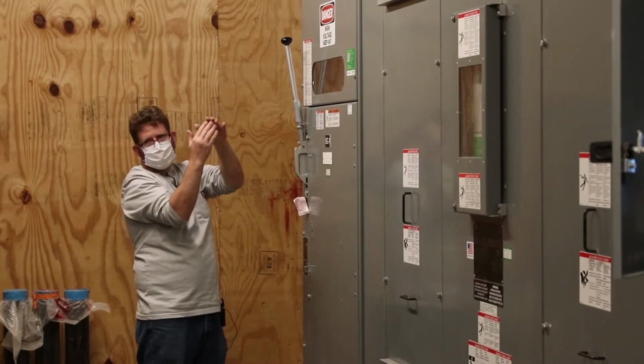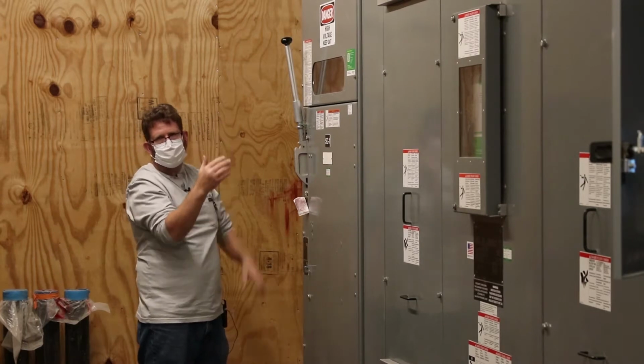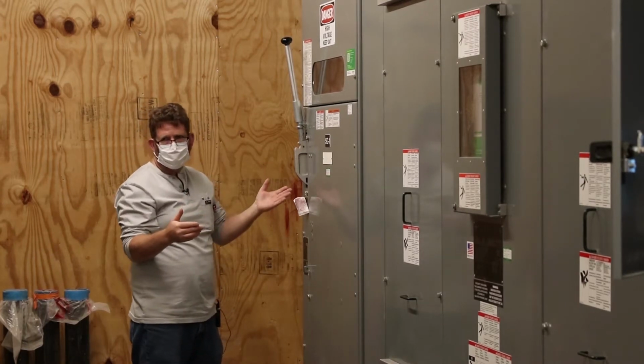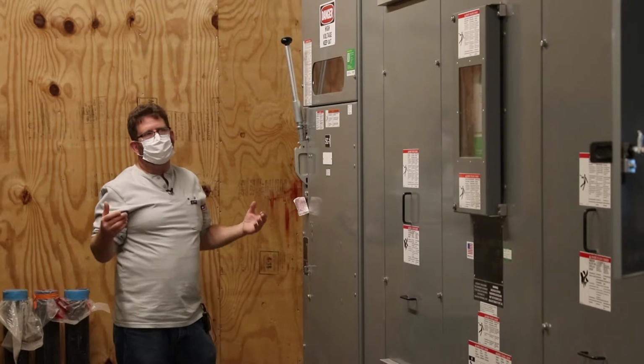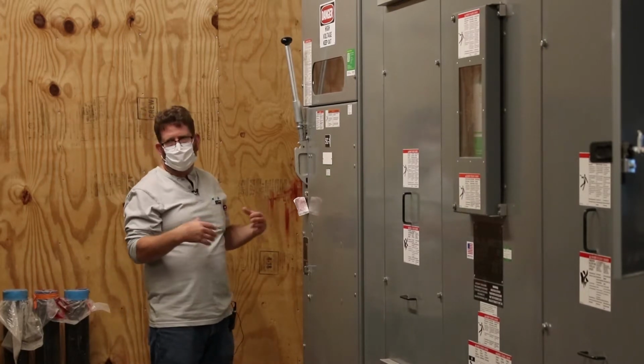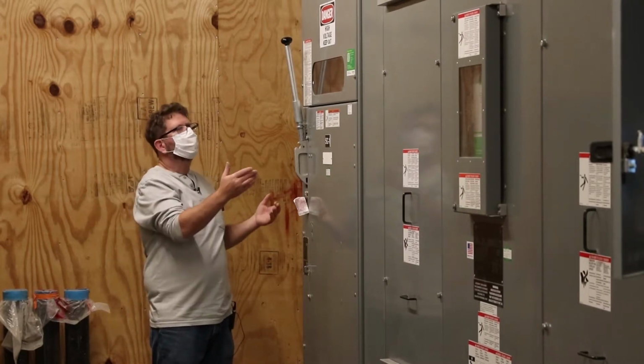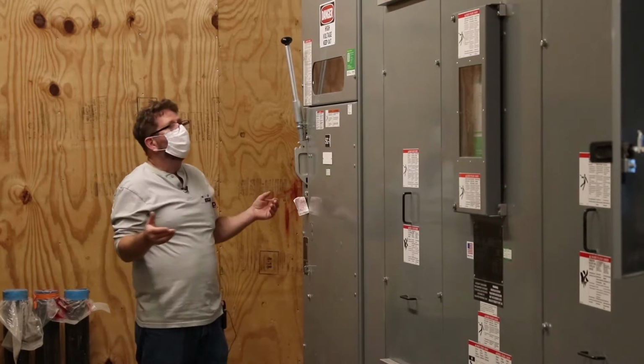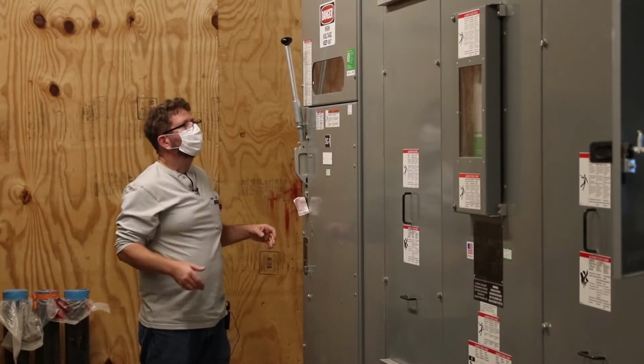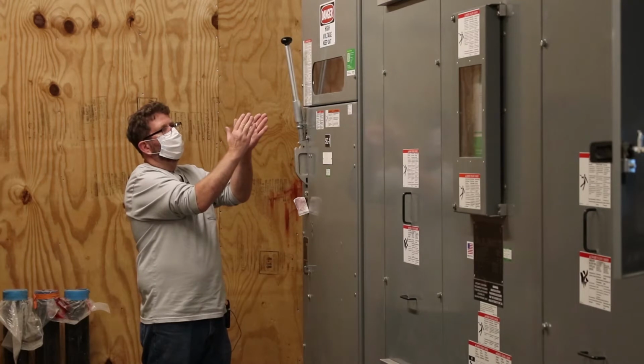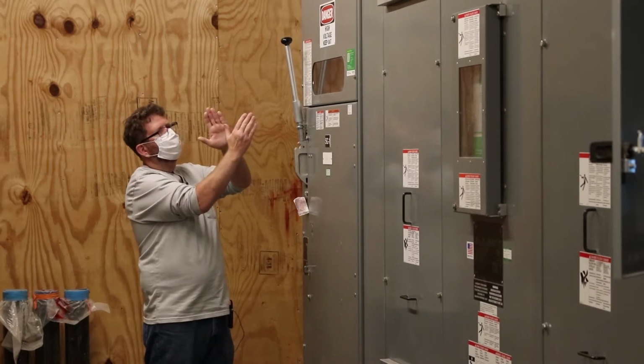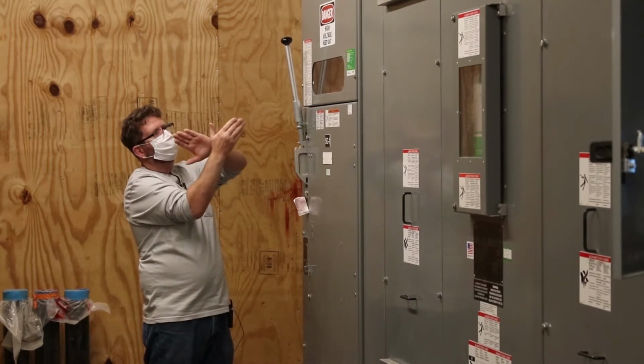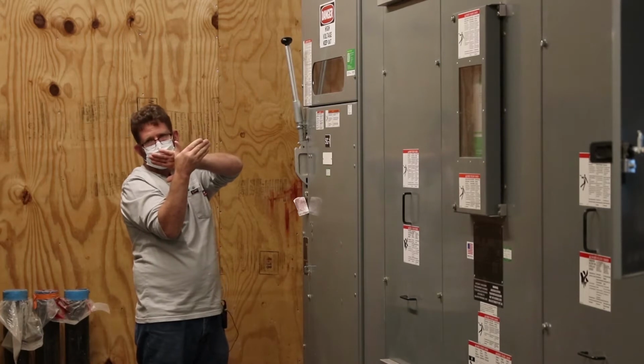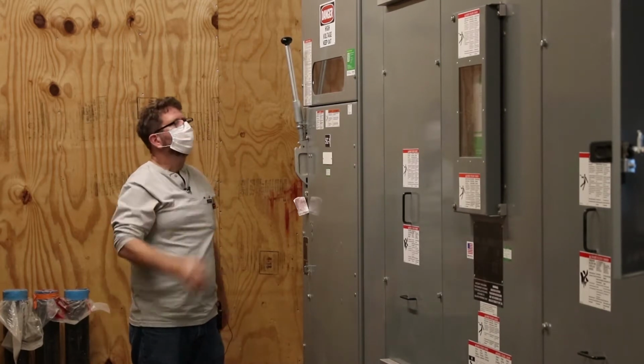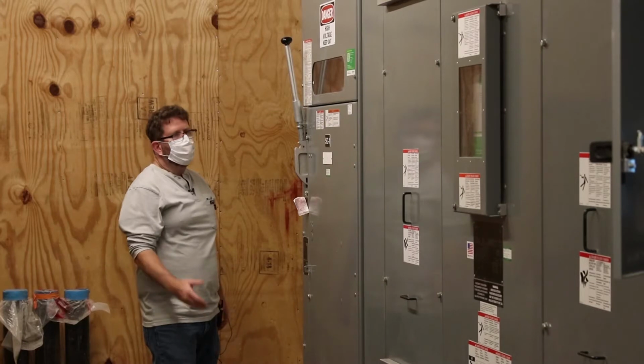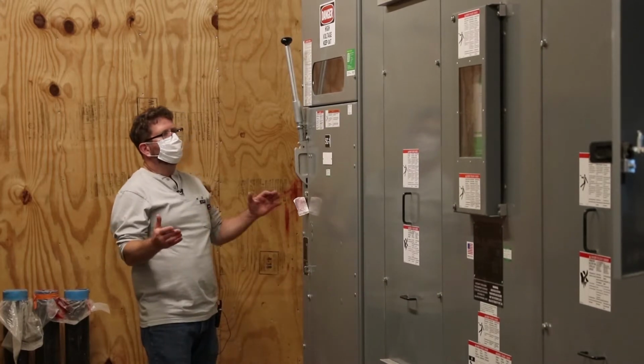And that's to keep any arc minimized to the arc tips instead of on the main blades. Every switch, every load break switch, any circuit breaker has an arc tip assembly. And they pretty much all work the same on switches. So on the opening, the main blade comes out. Once it gets far enough, the arc tip slips out, and you'll see the arc at the arc tip. On the closing, it works the same way, except backwards.